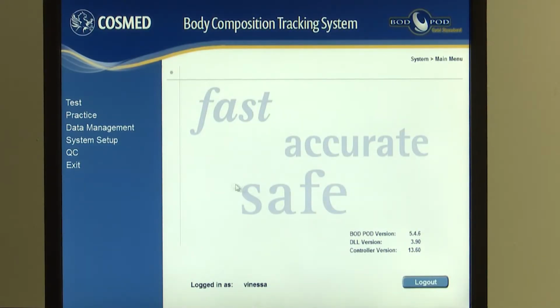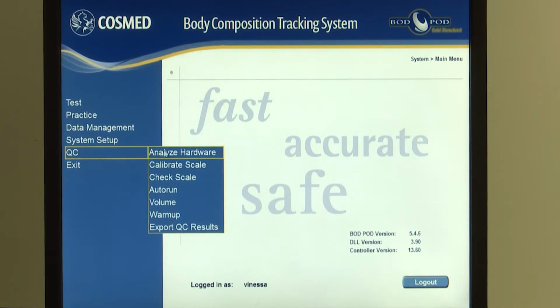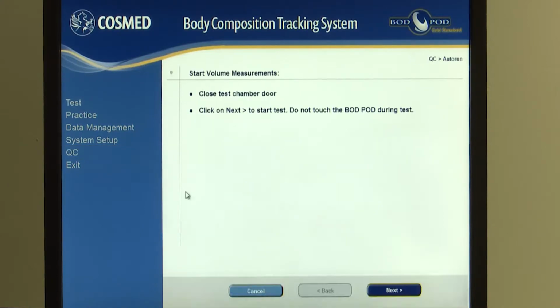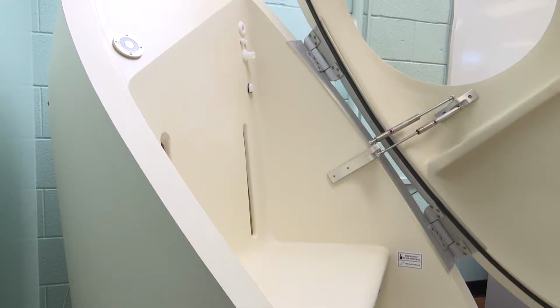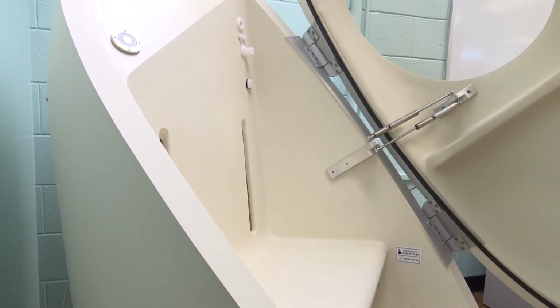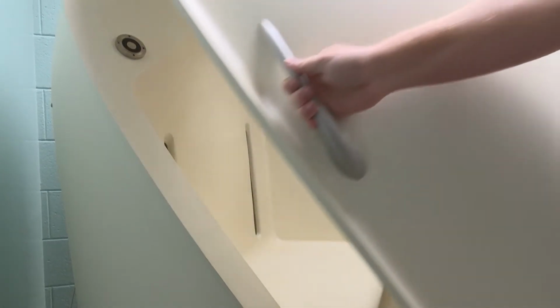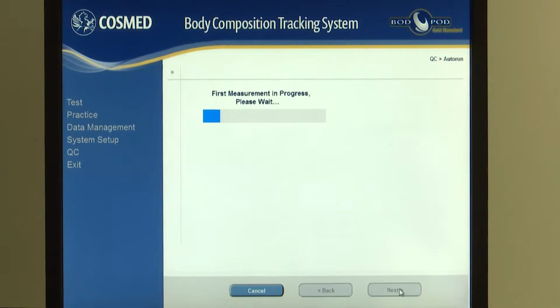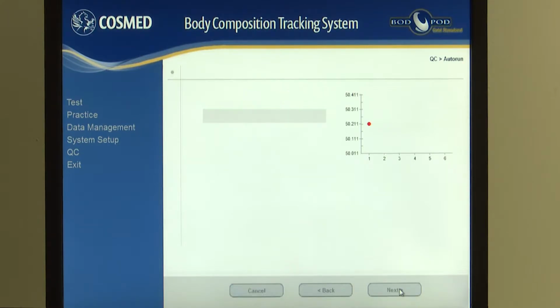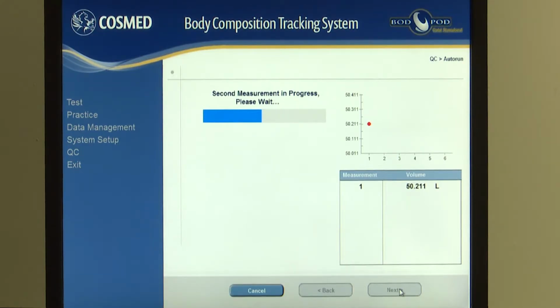Go back to the QC tab, open the drop-down menu, and click Auto Run. The software will take 6 measurements of the Bod Pod chamber and volume. Do not touch the Bod Pod at this time and do not open any doors during this process. After each measurement, the volume is displayed and must fall within the required values. Continue to follow the prompts on the Bod Pod computer screen and click Next after each step.